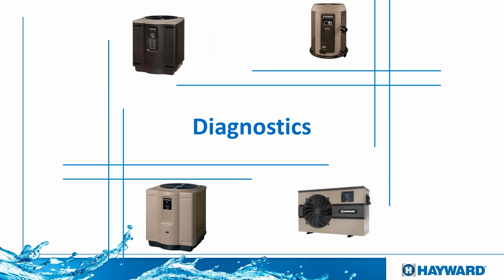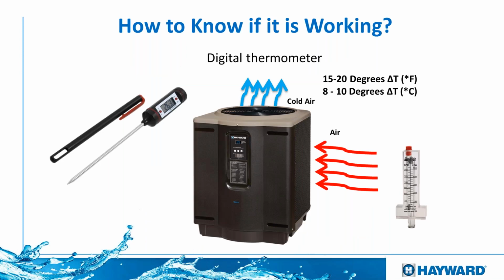Diagnostics. Let's talk a little bit about diagnostics. I'm going to be using a lot of pictures for this kind of presentation. It will make it a lot easier instead of doing a whole bunch of wires. But first of all, I want to tell you that if you want to know if your heat pump is actually working at 100%, you can do this test, which we call the delta test.